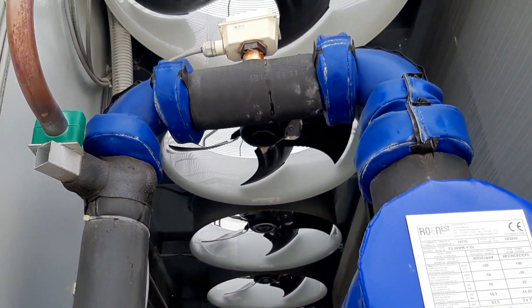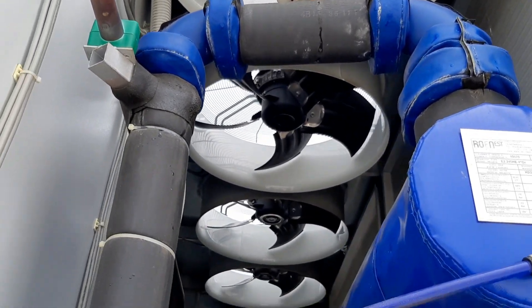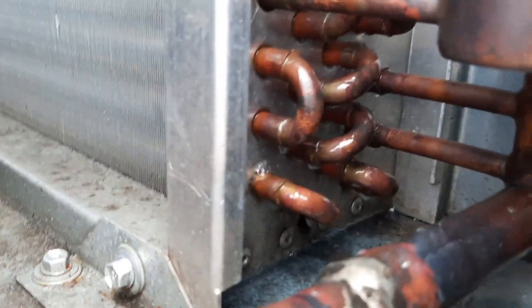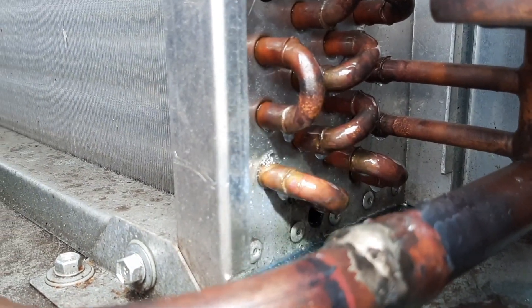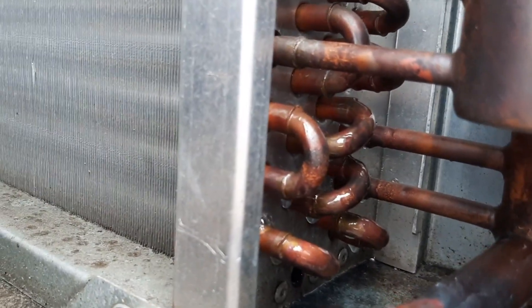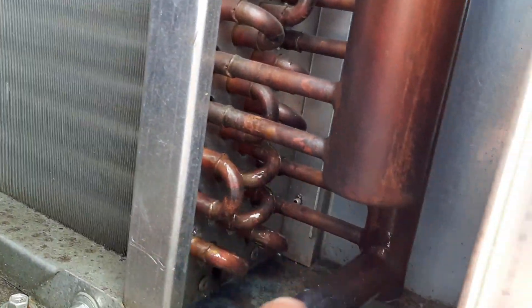It's probably 85 degrees out here now, and these fans should be cycling but they're not coming on. I'm sure it's running off of a pressure transducer or something back there. Oh yeah, there you go — there she is. She's right in between this plate and that condenser. That is liquid coming out.